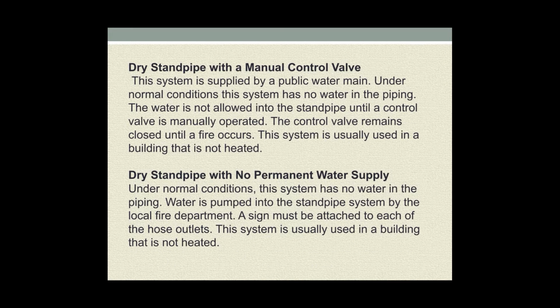Dry standpipe with a manual control valve. This system is supplied by a public water main. Under normal conditions, this system has no water in the piping. The water is not allowed into the standpipe until a control valve is manually operated. The control valve remains closed until a fire occurs. This system is usually used in a building that is not heated.